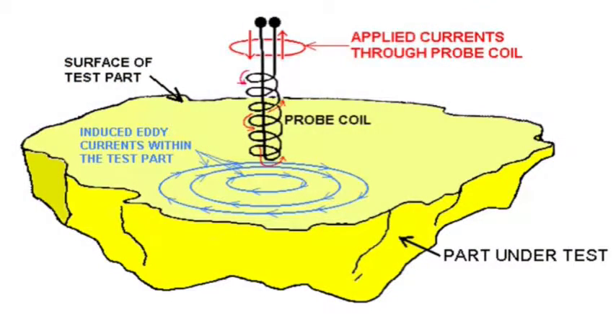Without getting bogged down in theory, we use the eddy current principle to measure conductivity. The sensor, or eddy current probe, is a coil of wire excited by an AC signal at a particular frequency. When the probe comes in contact with the metal surface, a secondary field is induced in the material. This is called an eddy current field. The ability of the electrons to flow in the material is then compared to known materials with known conductivity values. This information is processed within the instrument and a value in % IACS is displayed.